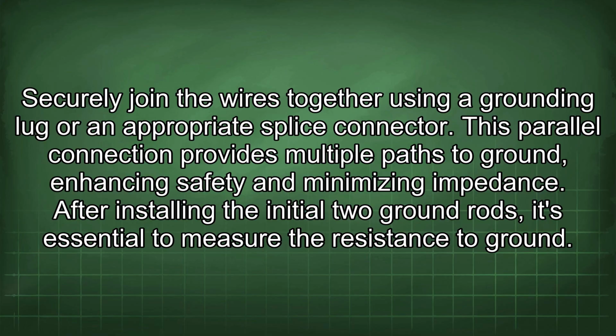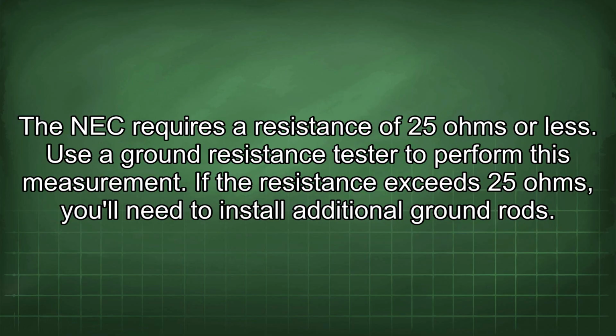After installing the initial 2 ground rods, it's essential to measure the resistance to ground. The NEC requires a resistance of 25 ohms or less. Use a ground resistance tester to perform this measurement. If the resistance exceeds 25 ohms, you'll need to install additional ground rods.